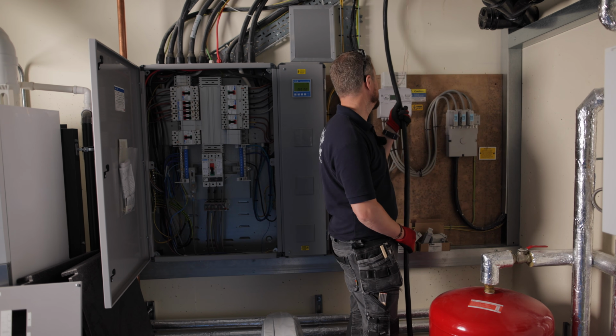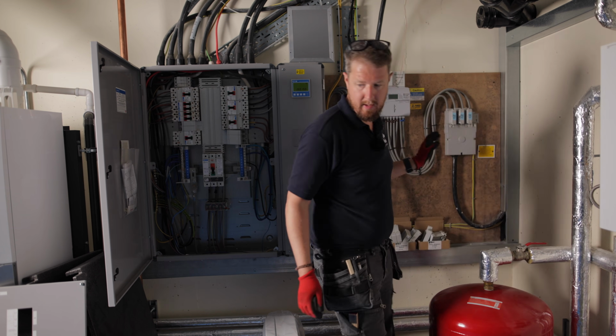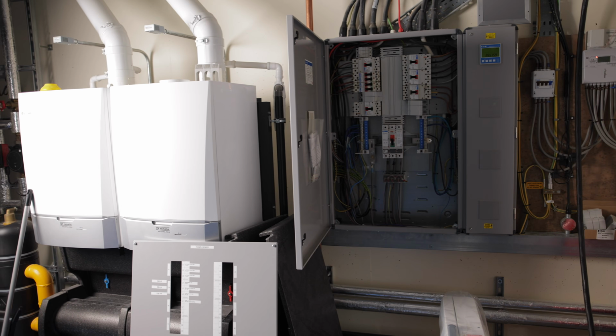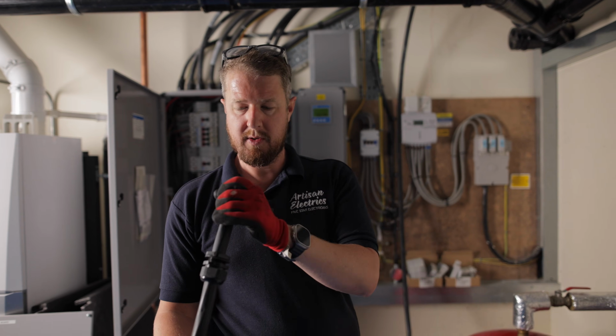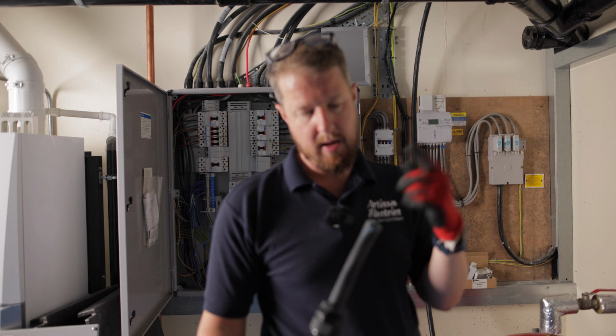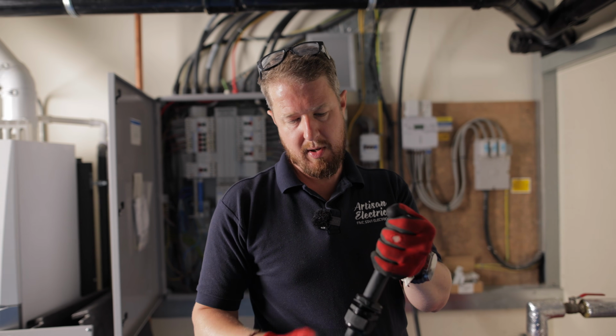This is the armoured cable that feeds the battery. And because we've earthed the armouring at the other end, because we've got an earth core within this, we don't need to earth it at both ends. So we're just going to put it in a stuffing gland at this side. But what I want to do is just get the gateway open, have a little look inside it.